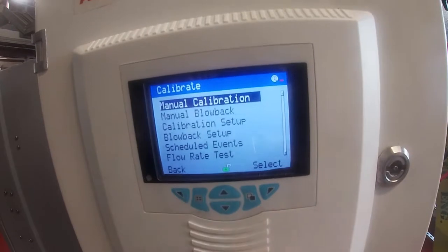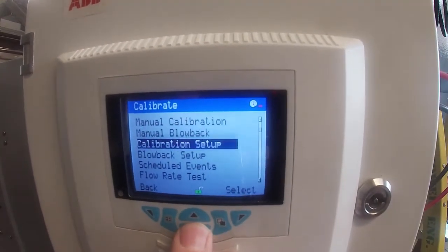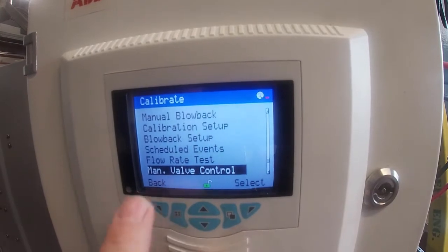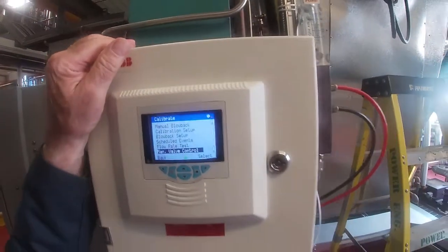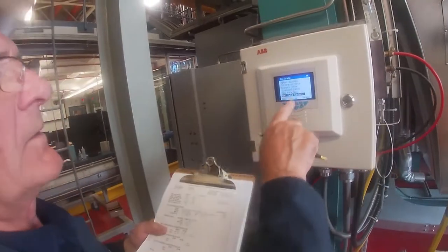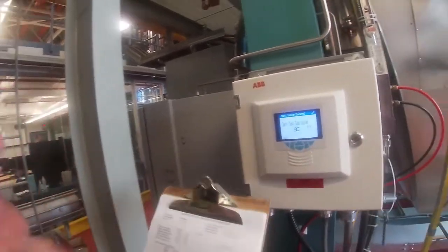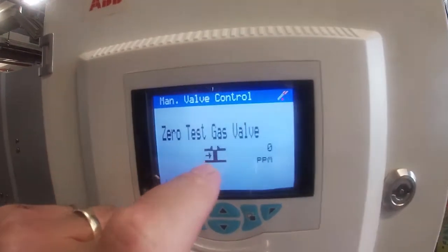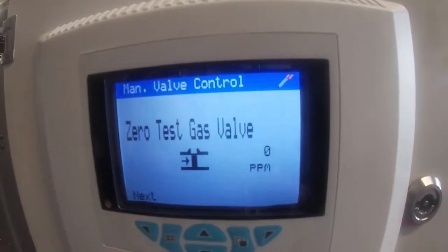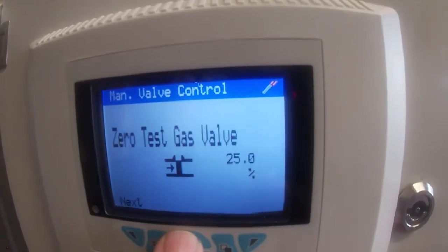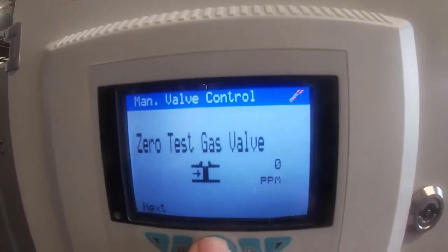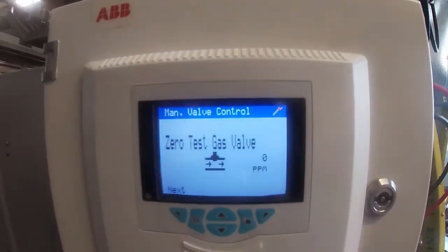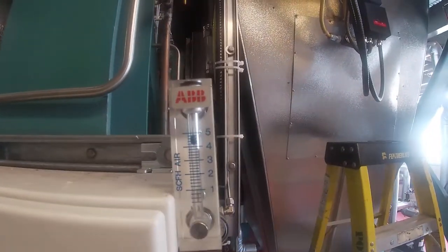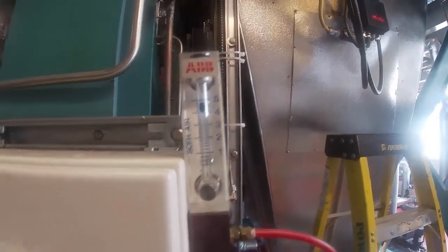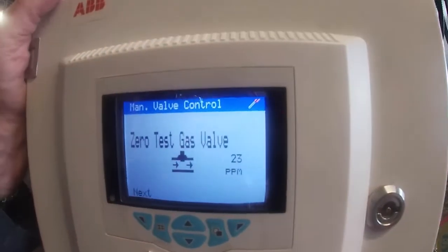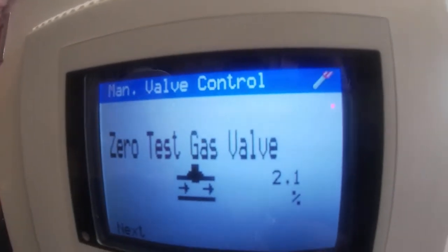Now I'm going to back out of here and go up to a manual calibration, manual valve control. I want to inject gas and compare it. So I'm going to hit select. It's kind of neat. It's actually going to put the zero gas in, and you're going to see it pop open that little valve and then show us what the O2 reads. I'll hit the up key, and you'll see that my valve just opened. I've got test gas going through there at 4.5, and you can see now that the O2 is changing. It's gone down to 2.3, 2.1.